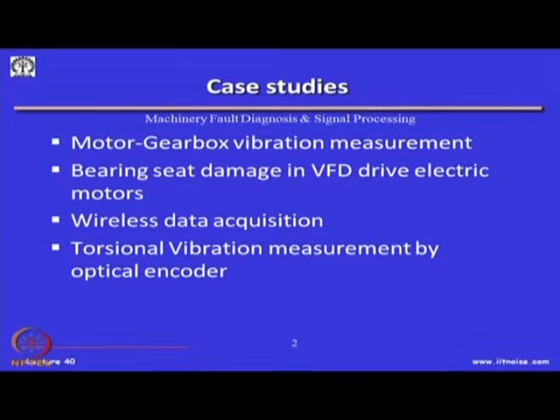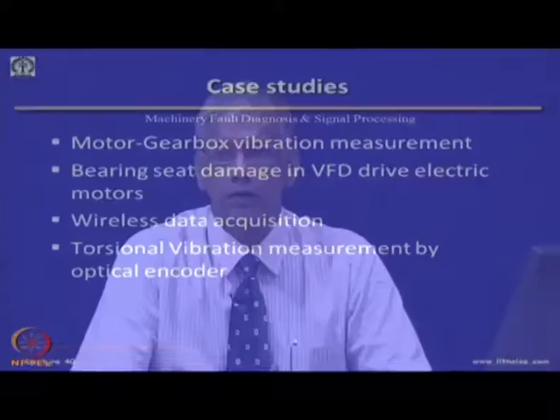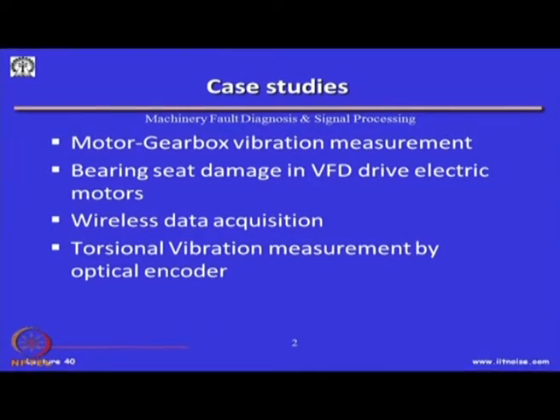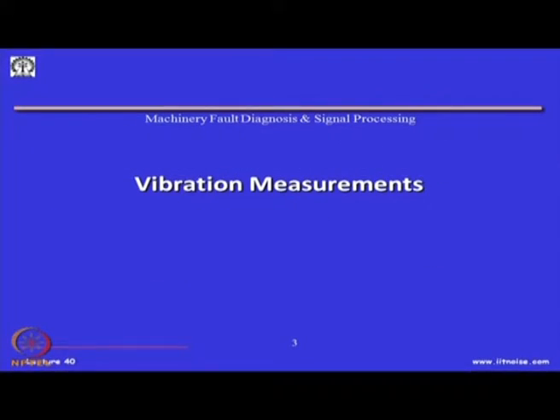Another emerging area is monitoring the health by torsional vibration. In ISO standards and mostly in this class, we have talked about linear vibration measurements, but recently there have been techniques where people have used torsional vibration measurements to find out faults in machines. Unlike the accelerometers used to measure linear vibrations, torsional vibration measurements using simple optical encoders are a very cheap method for such analysis. Now I will come to the very first case study on vibration measurements.